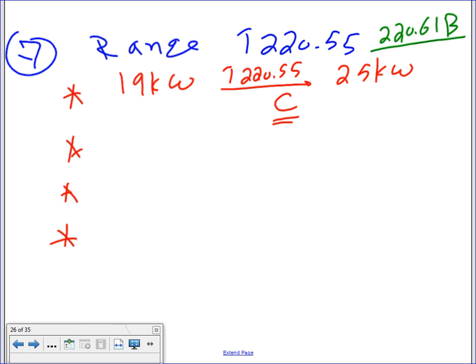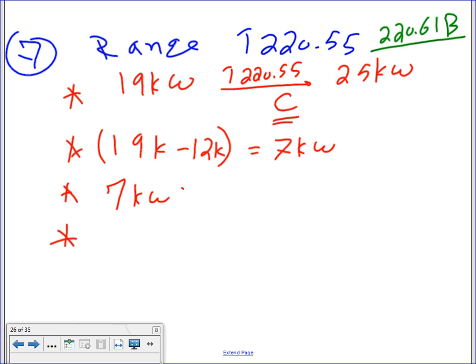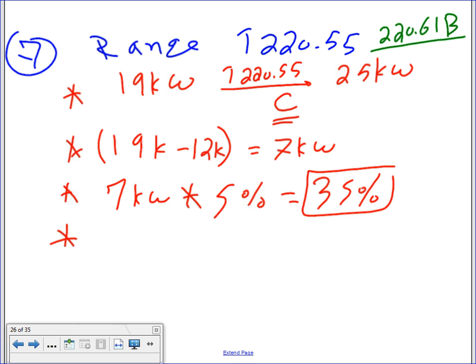That's a 25 kW. Then, step 2, you take the 19K, subtract from it 12K, because the code says so, equals 7 kW, the difference between the 12 and what I have. Then take every 7 kW, multiply it by 5%, because that's the difference between what I have and what the 12 is. That will get you a 35% increase. So that's your increase. Your total demand, ladies and gentlemen, is 1.35 multiplied by 25K.